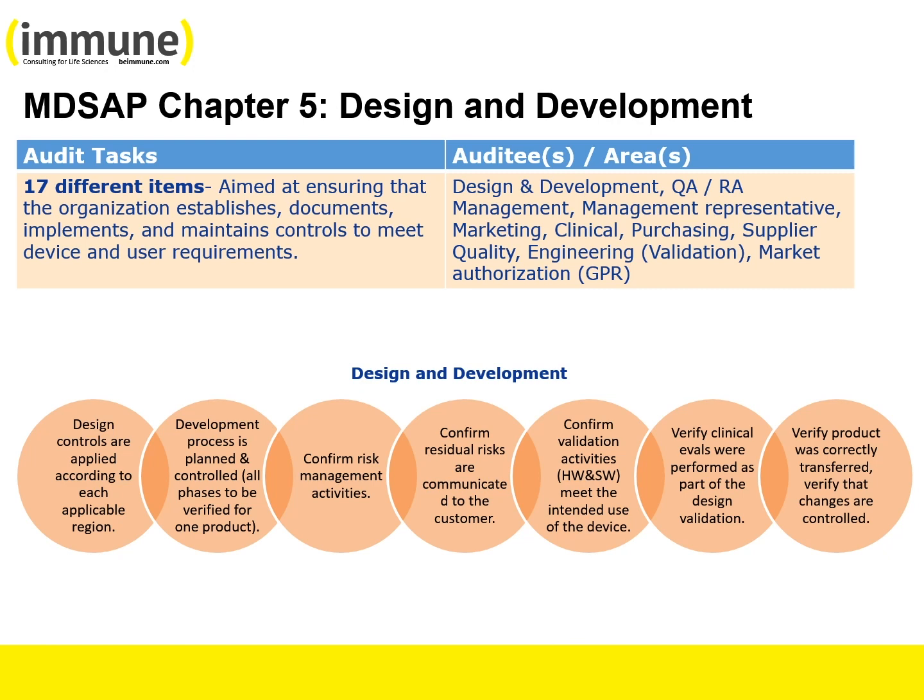verified that design outputs satisfy the design input requirements, identified and mitigated to the extent practical the risks associated with the device, including the software, which is part of the device function if applicable, ensured that changes to the device design are controlled with risks associated with the design change, identified and mitigated to the extent practical, and that the device will continue to perform as intended, performed design validation to ensure that devices conform to the user needs and the intended use, and confirmed that the design is correctly translated into the production methods and procedures required.